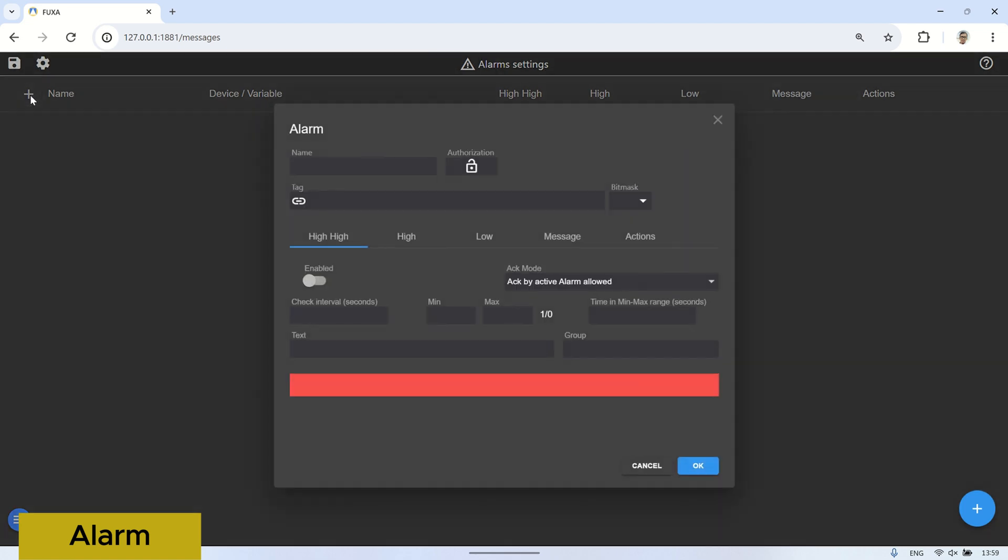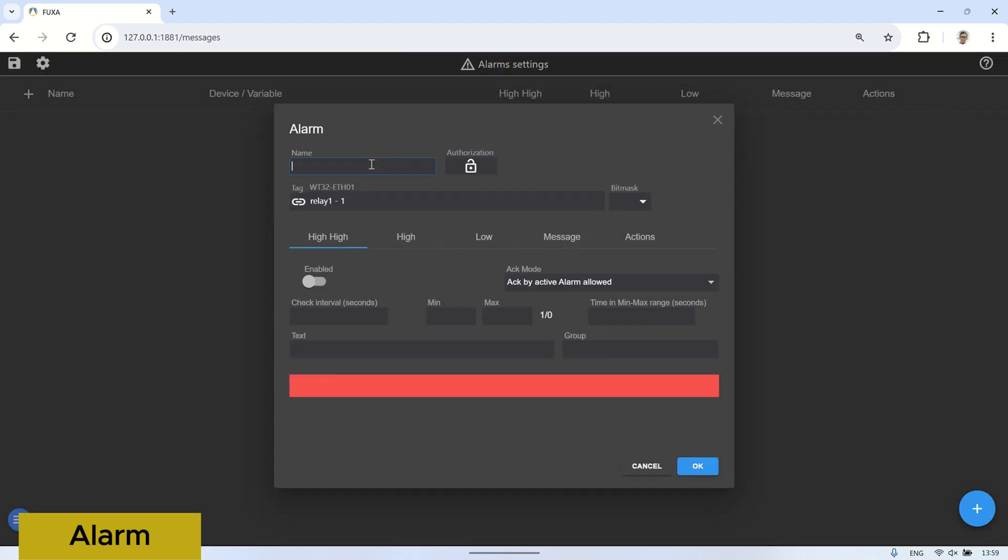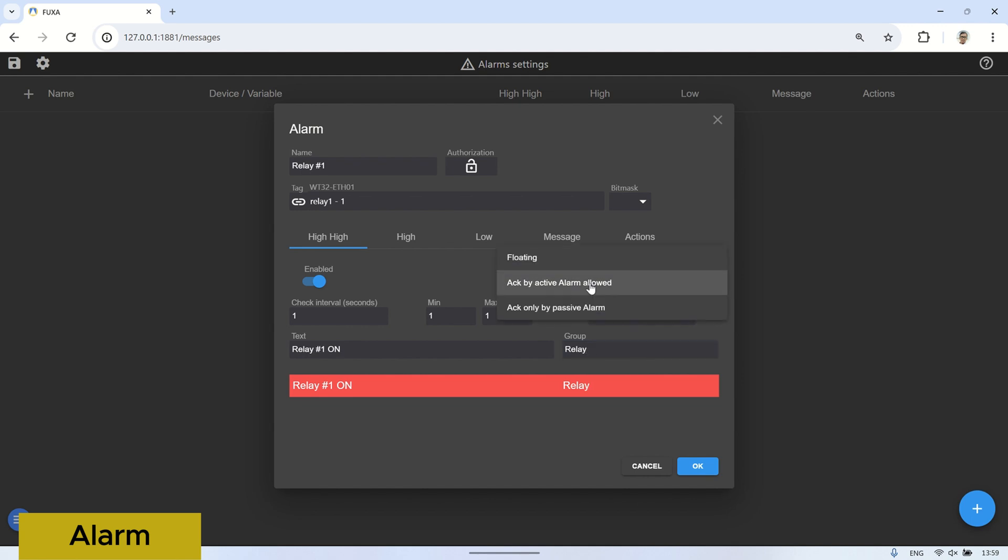Next, I'll create an alarm. Click on alarm in the setup window to open the alarm settings page. In this alarm settings page, I'll create an alarm if relay number one and relay number two are activated. Apart from being an alarm for true or false status, alarms can also be set based on value ranges. For example, for temperature, we can set an alarm to trigger if the temperature value is between 30 to 100 degrees.